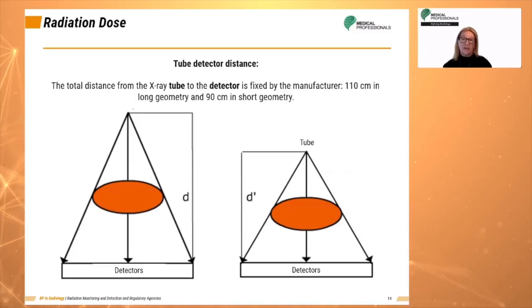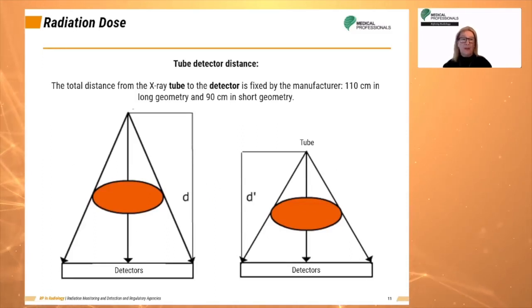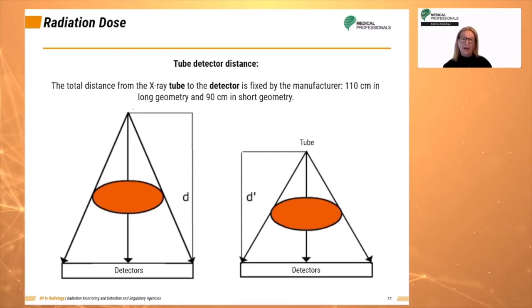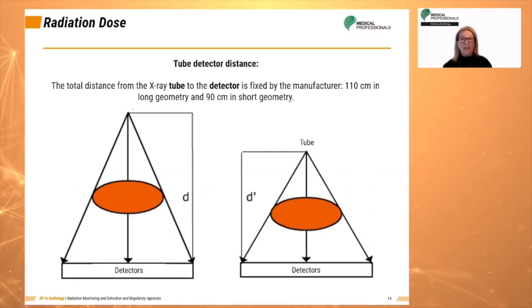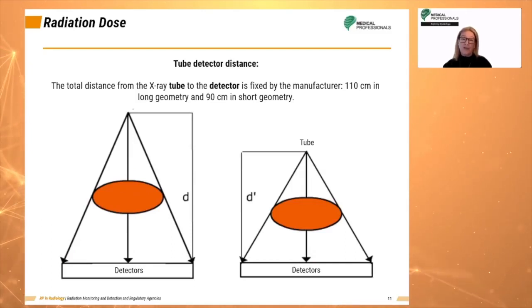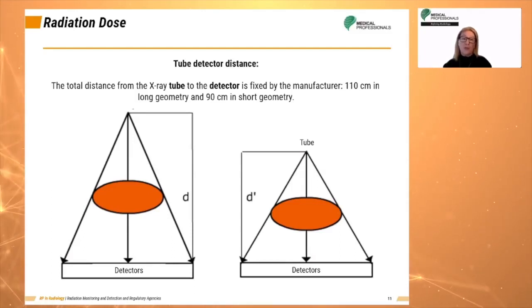The total distance from the x-ray tube to the detector is fixed by the manufacturer: 110 centimeters in long geometry and 90 centimeters in short geometry. It requires a higher MA value in long geometry since the dose is inversely proportional to the square of the tube-detector distance. Future CT generations are designed with short tube-detector distances to reduce patient radiation dose.